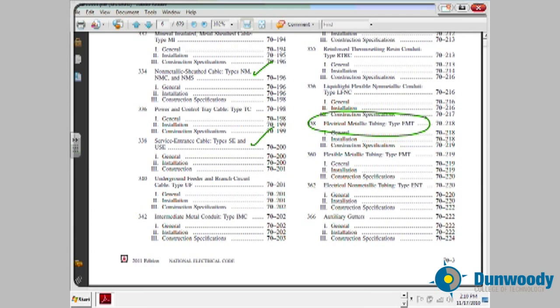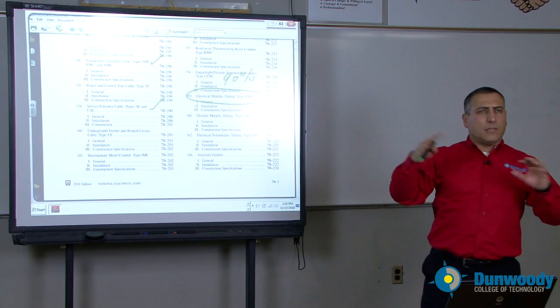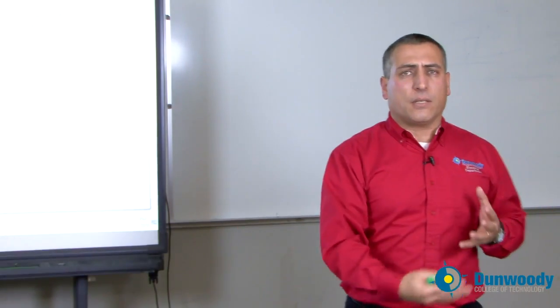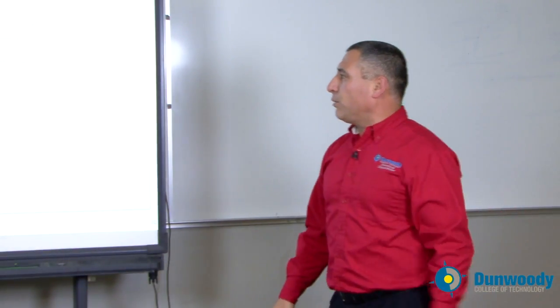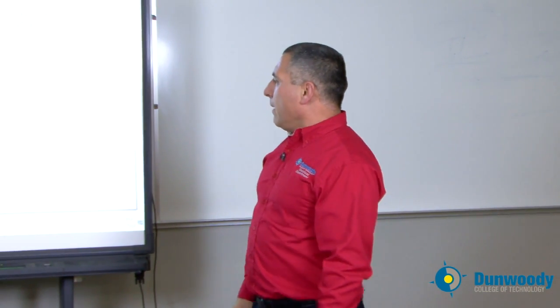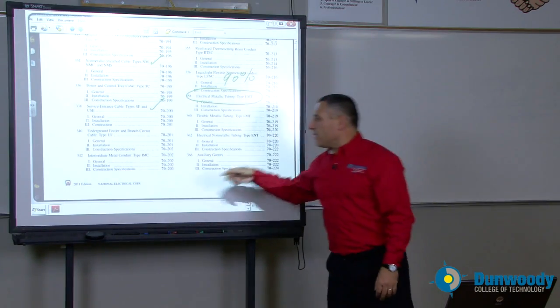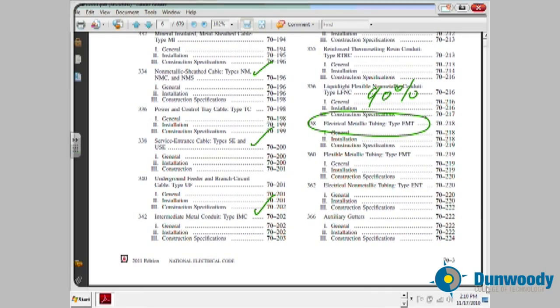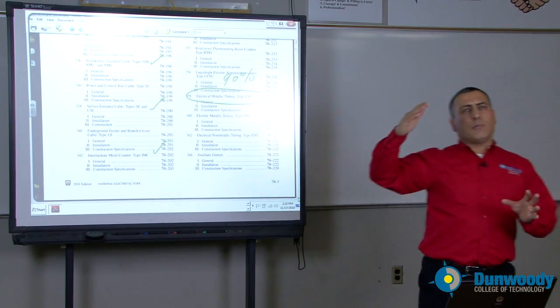EMT — almost 90% of your commercial and industrial building is going to be wired with EMT. Everything inside can be wired with EMT unless you need physical protection or you're going underground. So that's your conduit of choice; you need to know everything about this type of conduit. IMC is another very important conduit if you want something between EMT and rigid metal conduit.